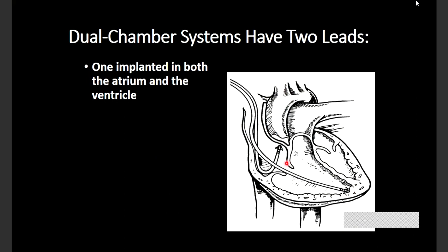The basic difference in a dual chamber pacemaker is that because you have two leads, this can sense the atrial events and that can be timed to the ventricle events. So it will sense an atrial event, either an intrinsic atrial beat or a paced atrial beat, and based on that, after a set time interval of 120 milliseconds or 150 milliseconds, it can pace the ventricle. So how do you differentiate a dual chamber from a single chamber ECG? In a dual chamber pacemaker, there's always synchrony.